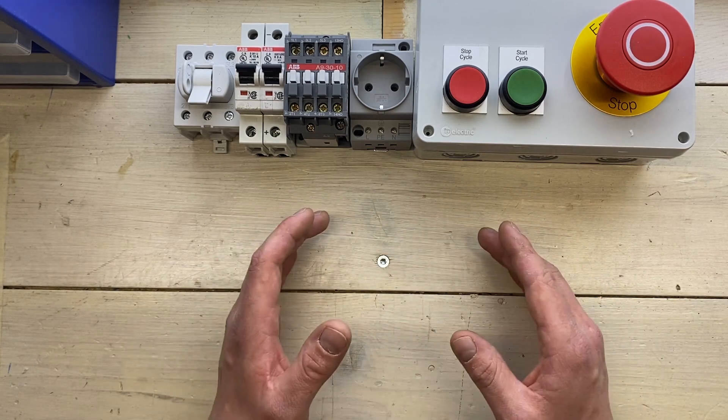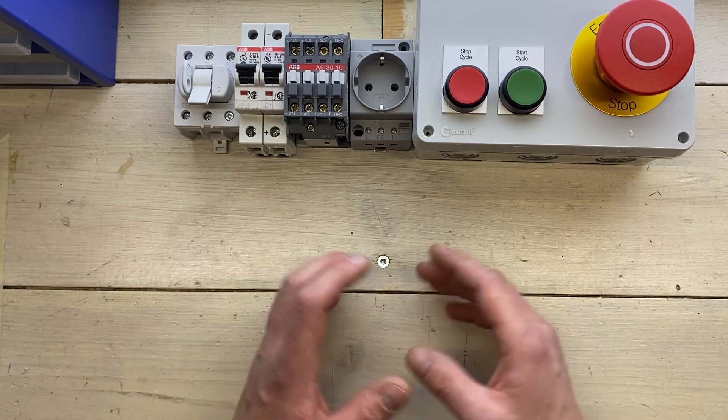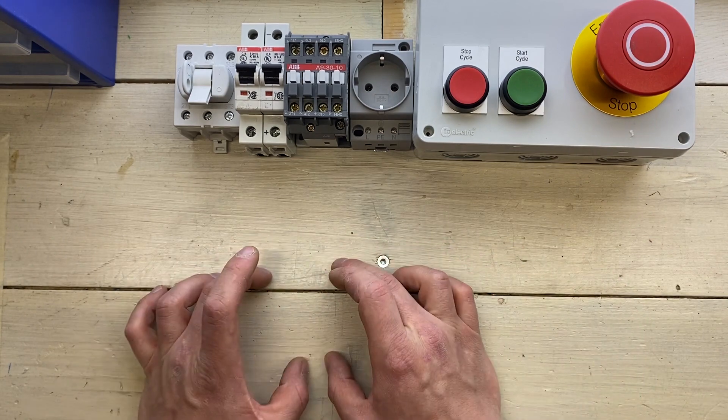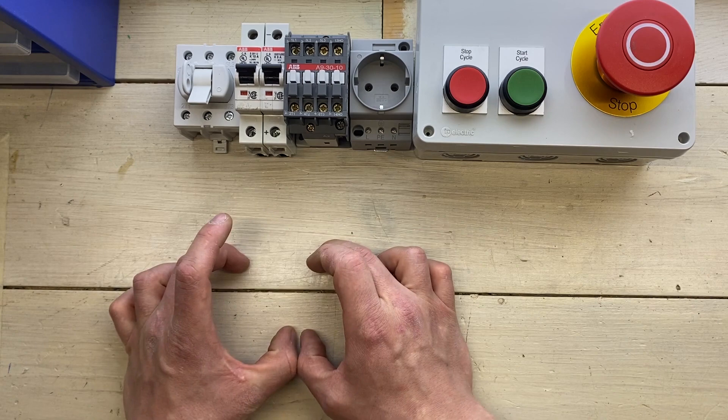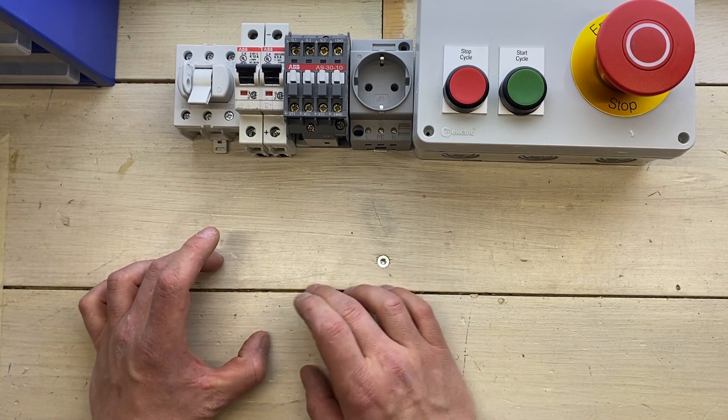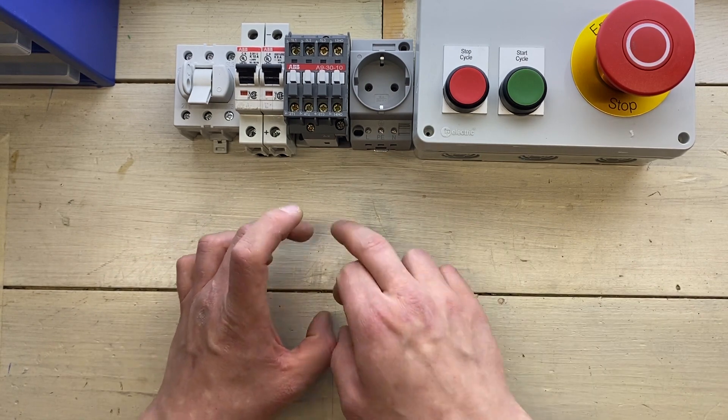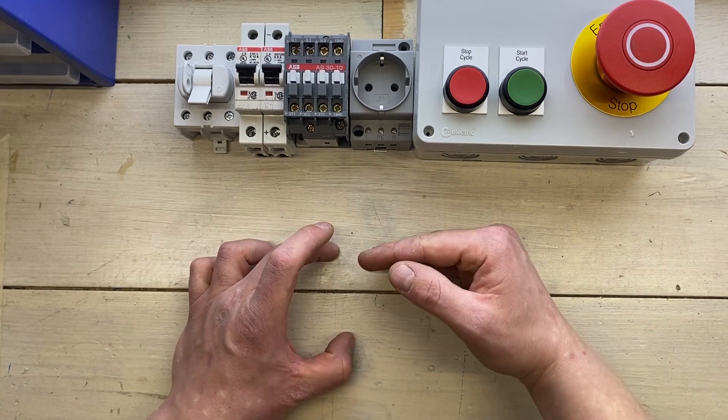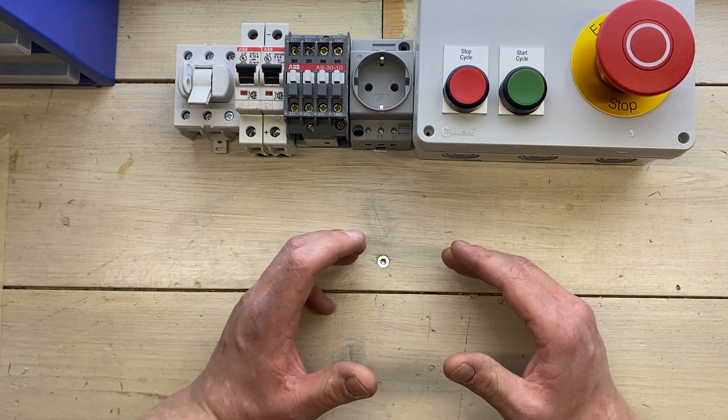But some of the steps I know has to be fulfilled is that you have redundant circuitry. So basically in a safety PLC designed to handle e-stops and other safety functions, you basically have an entire redundant CPU, which means if the first CPU crashes, the second one takes over and finishes the task or puts the machine in a safe state. And the same is with the input outputs, the Ethernet communication. Safe Ethernet communication means you have two separate communication hubs that can talk independently of each other. So if one fails, the other takes over. And this is also true in safety relays.